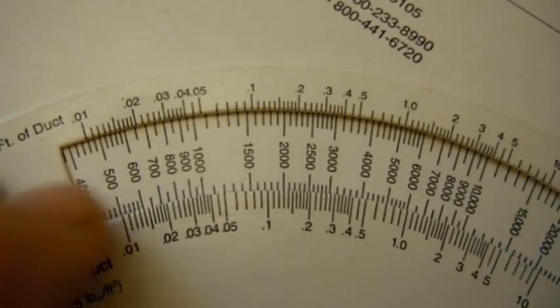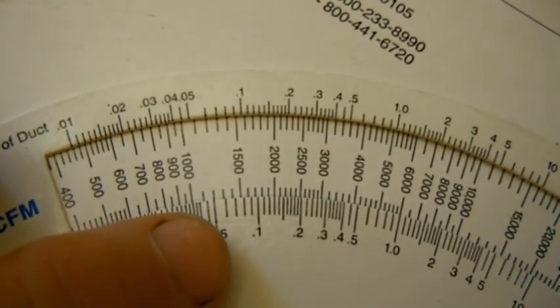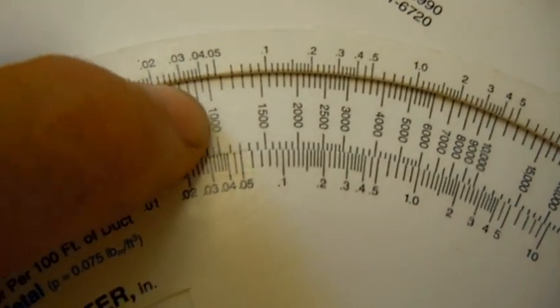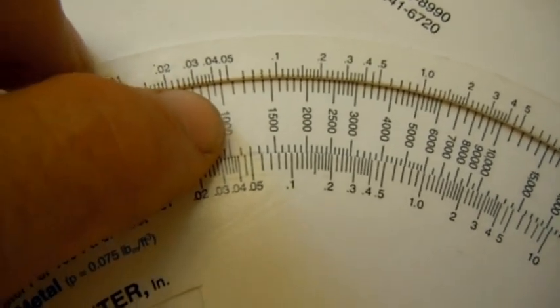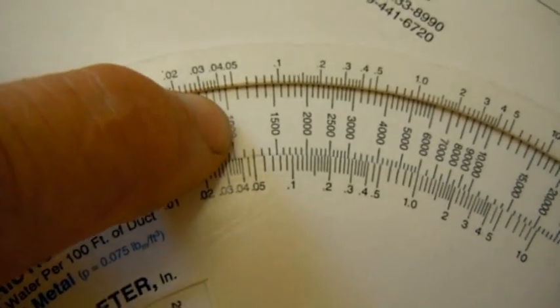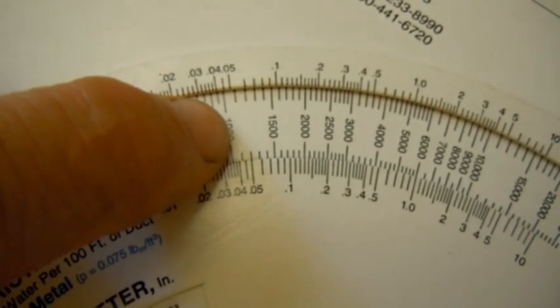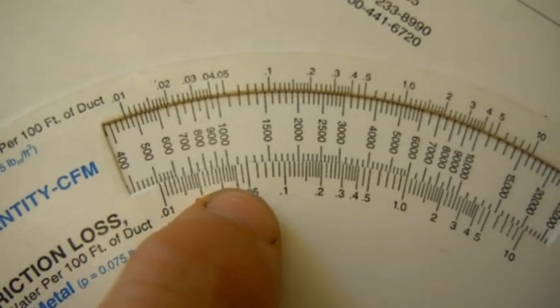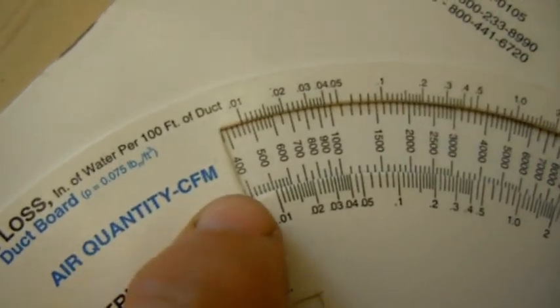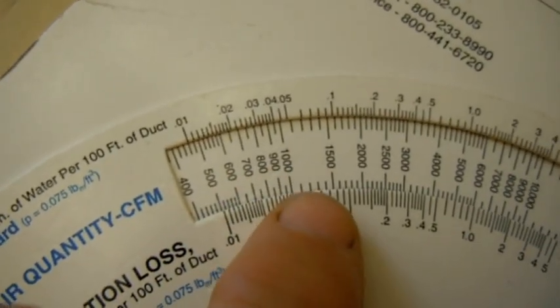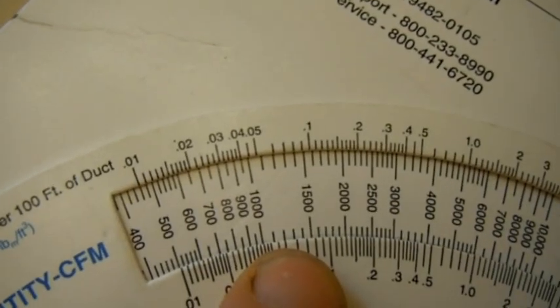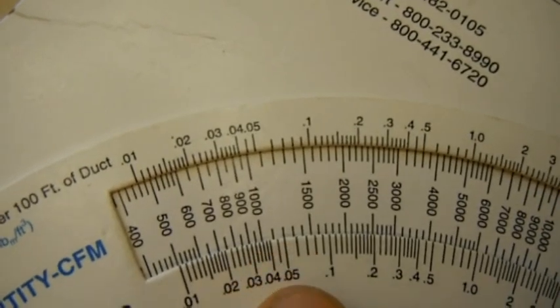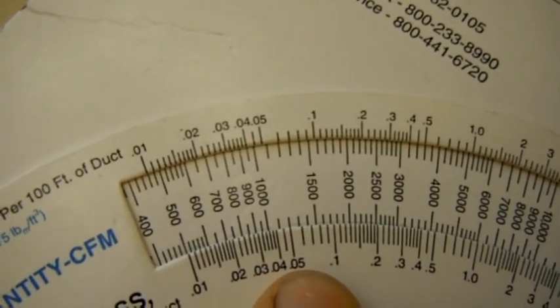And you have a three ton air conditioning system. Rule of thumb, every manufacturer is different, but rule of thumb is that there's 400 CFMs per ton of air. So let's say your CFMs are at 1,200, because three tons, that's three times 400 is 1,200 at .05.